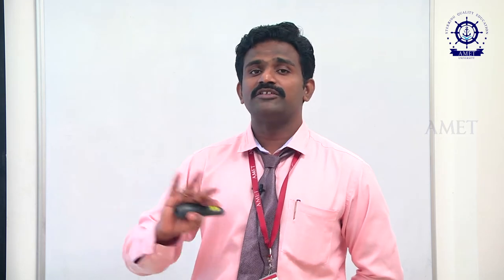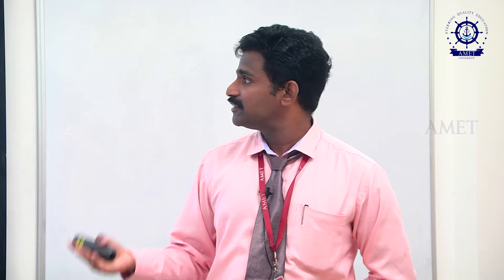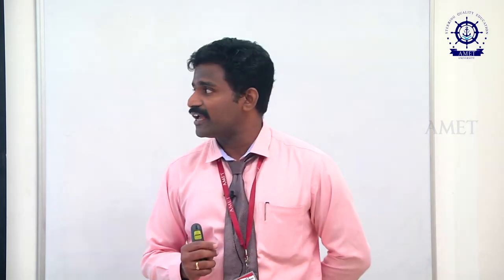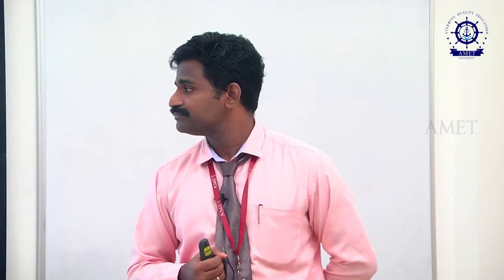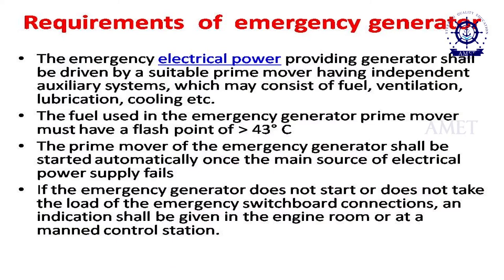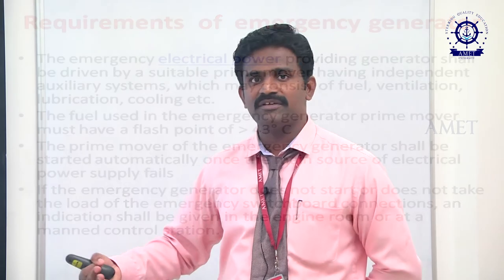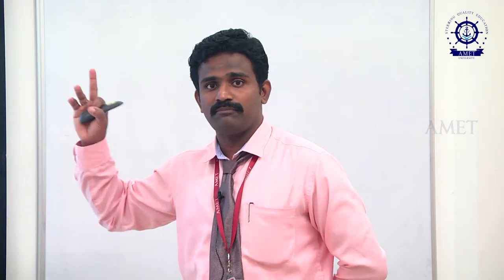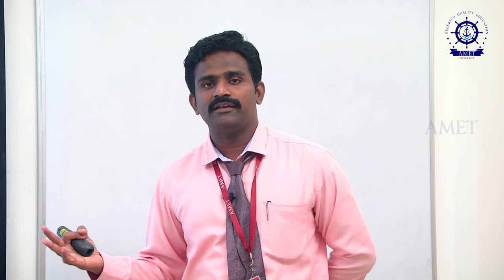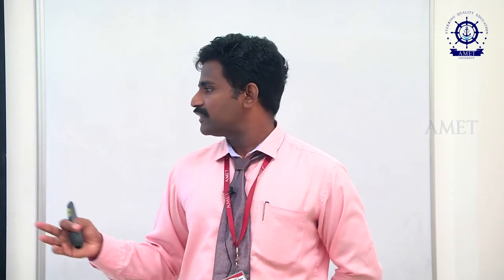The emergency generator must be independent and not combined with other generators. The fuel for the prime mover must have a flash point of greater than 43 degrees Celsius. The prime mover shall start automatically once the main electrical power supply fails. If the emergency generator does not start or does not take the load of the emergency switchboard, an indication shall be given in the engine room or at the manned control section so the chief engineer can take quick action.